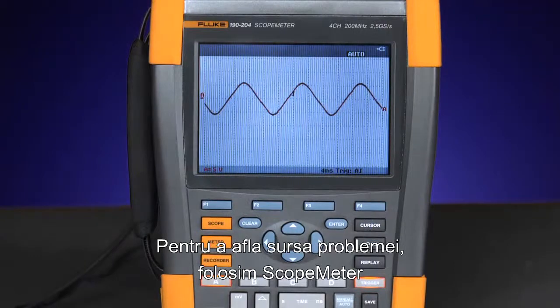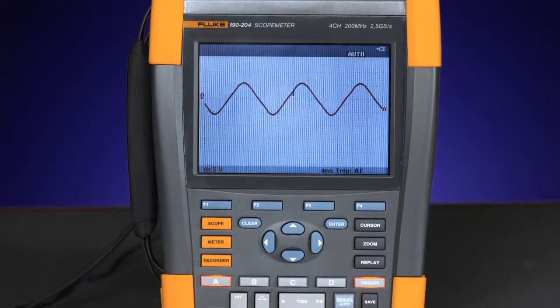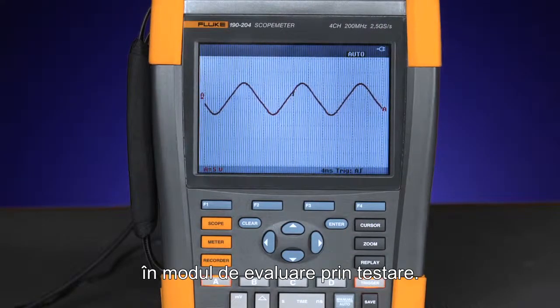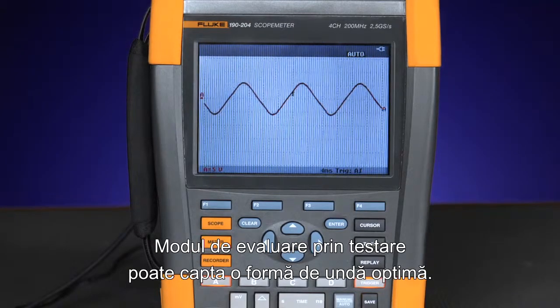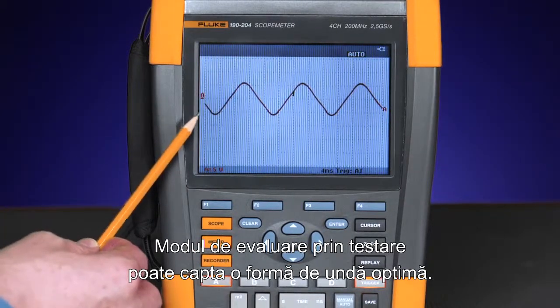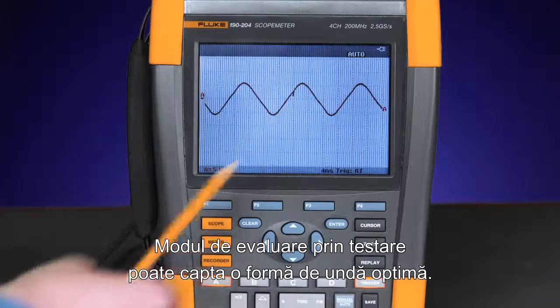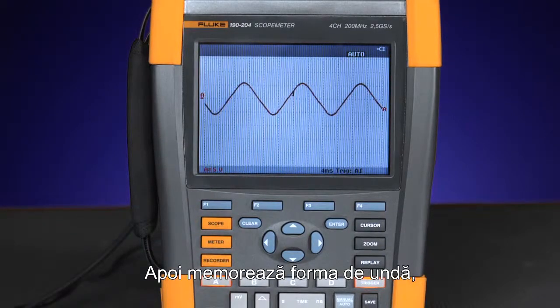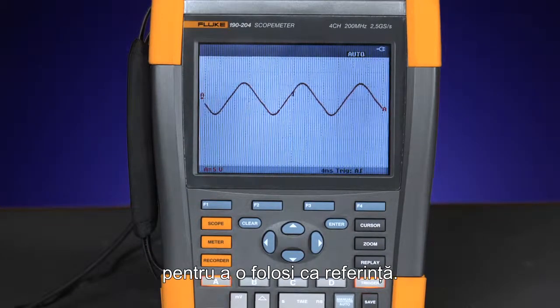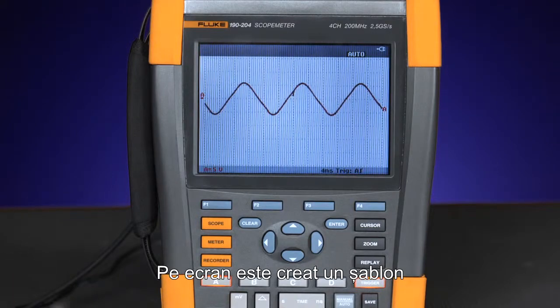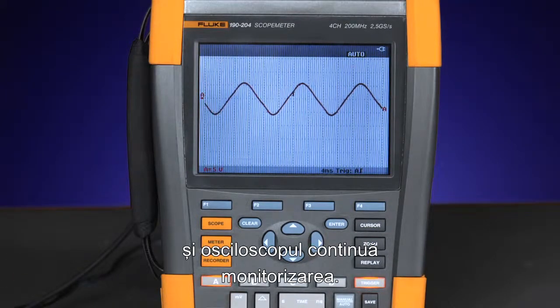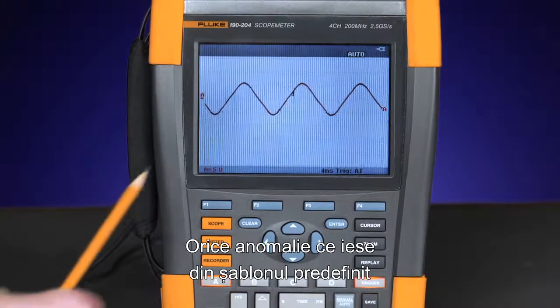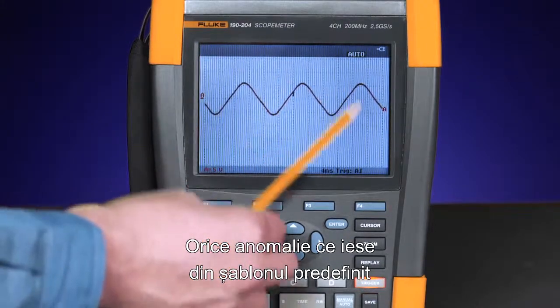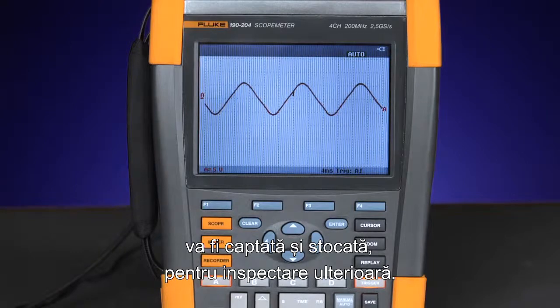To get to the root of the problem, we're going to use the ScopeMeter's pass-fail testing mode. The pass-fail testing mode has the ability to capture the waveform in a known good state. It then stores the waveform into memory to use as a reference envelope. The envelope is created on the screen, and then the oscilloscope continues monitoring.